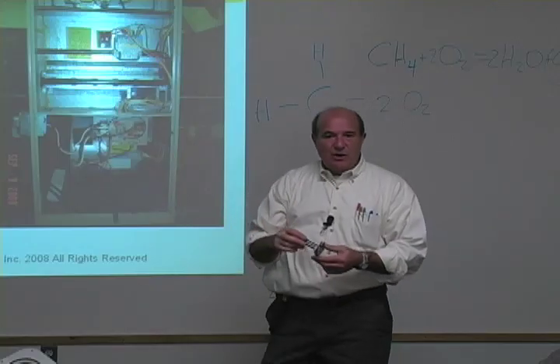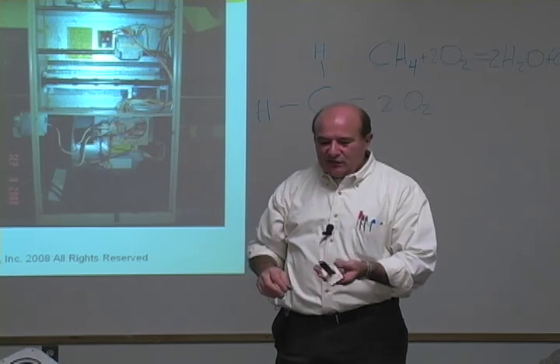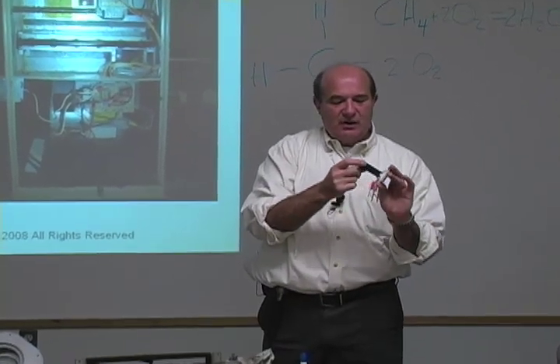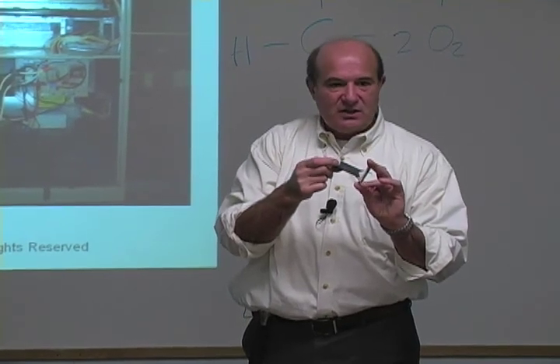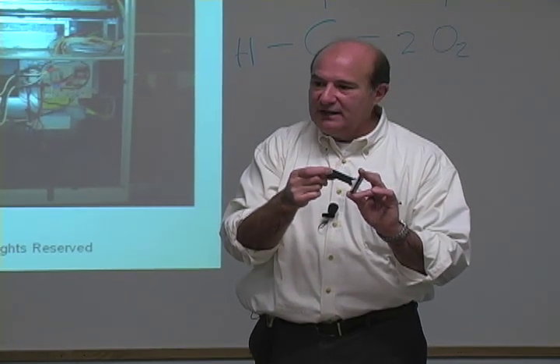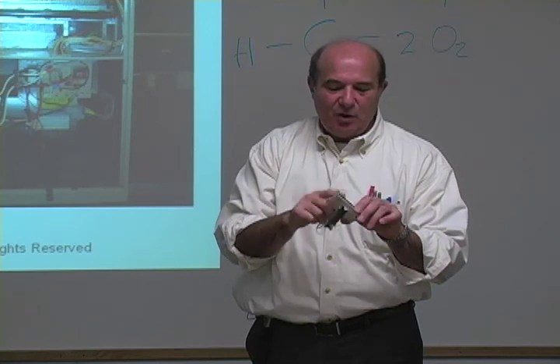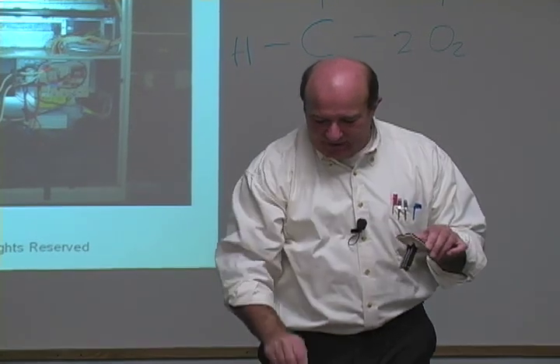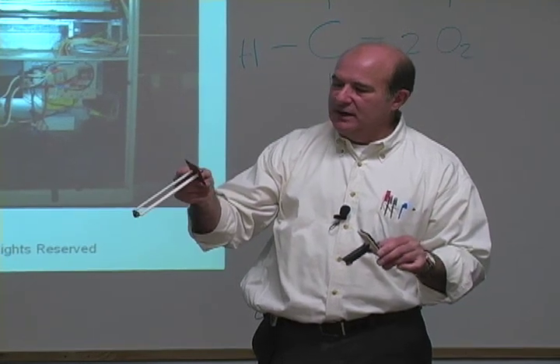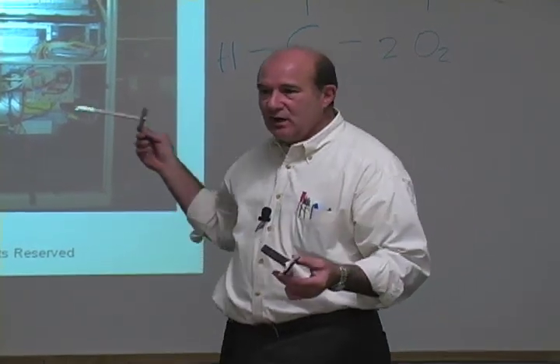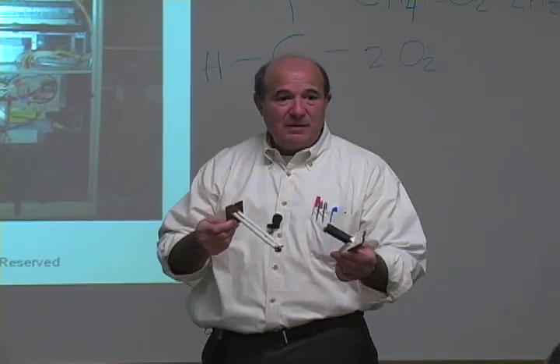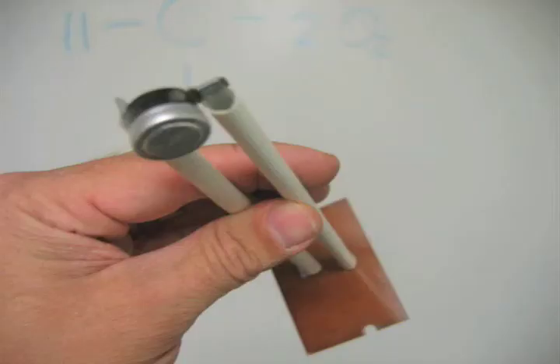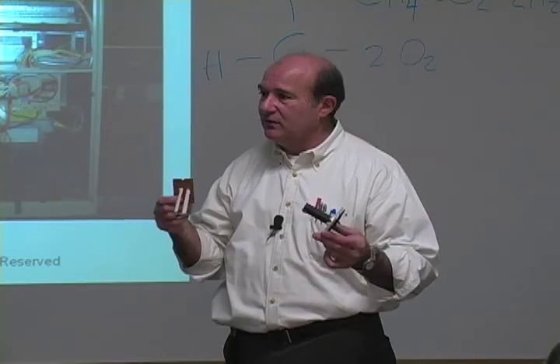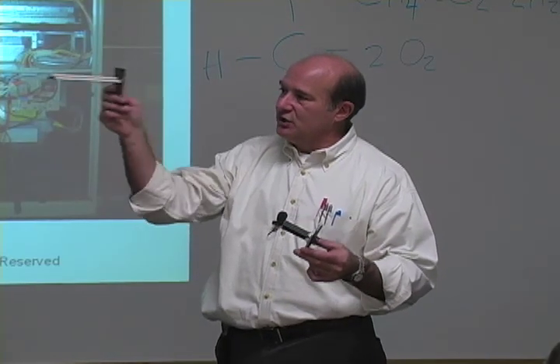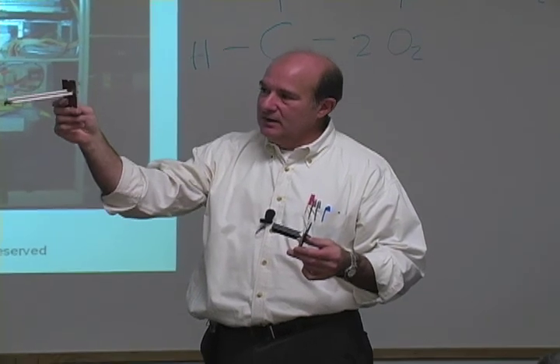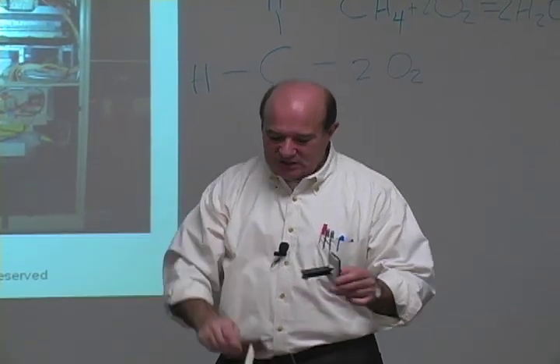If for any reason we have a blower failure or some reason that heat exchanger overheats, this little heat sensor over here, we call this a snap disc. This little snap disc will overheat, and it will pop and it will open up the connector on this circuit. Here's a second one. This is an auxiliary switch. A lot of these furnaces will have 2 or 3 or maybe even 4 of these types of limit controls at different locations on the furnace. This one looks like it's an insertion inside a heat exchanger. This is the limit switch that we see up here.